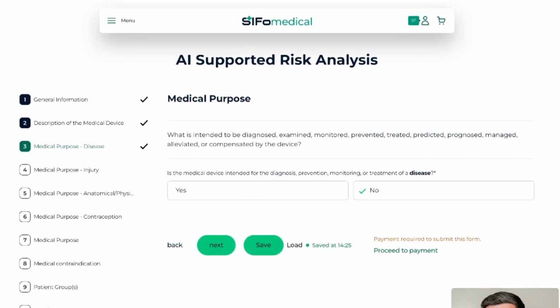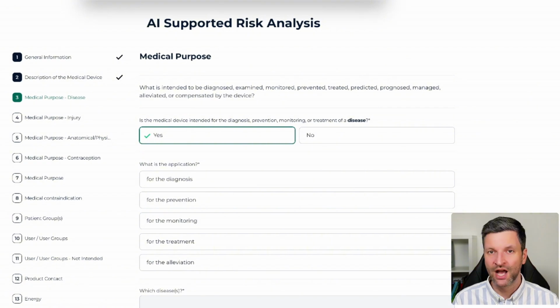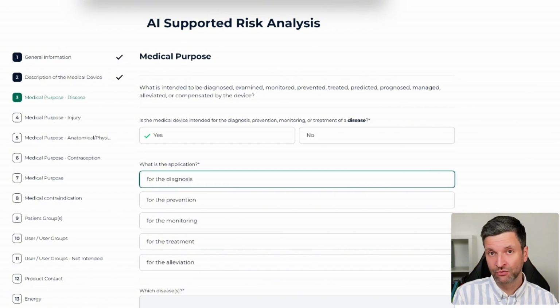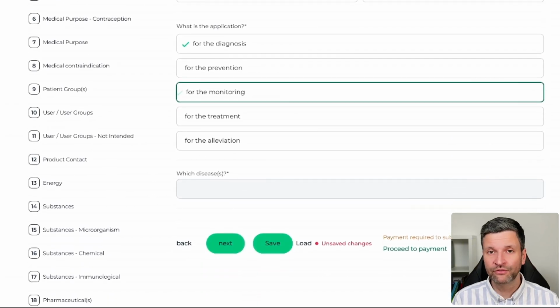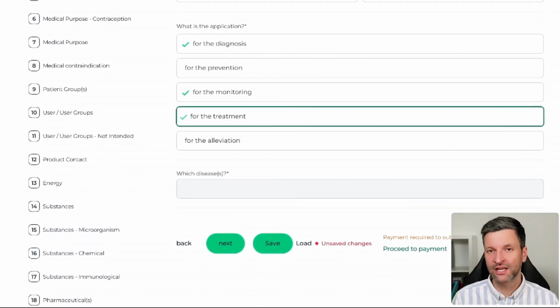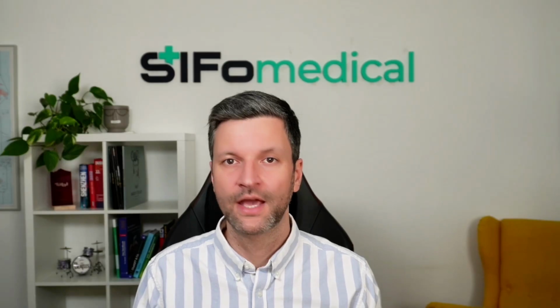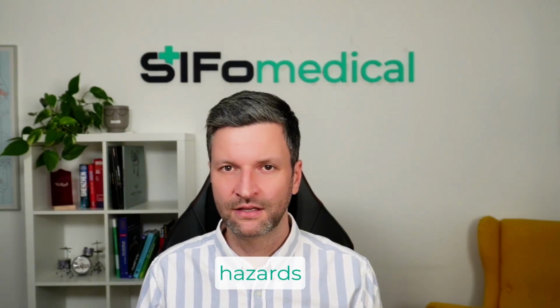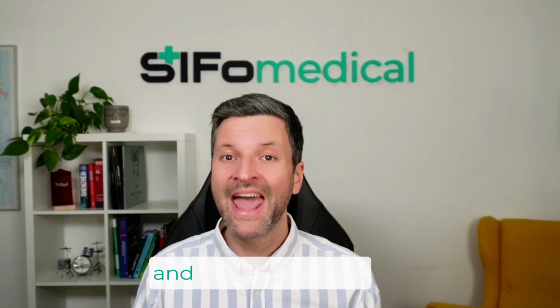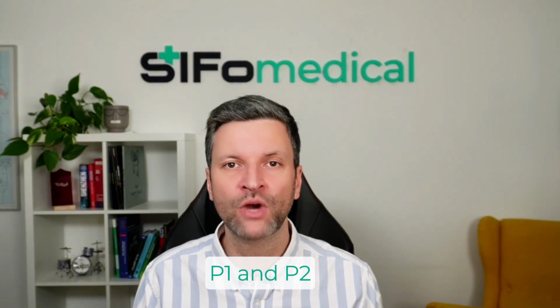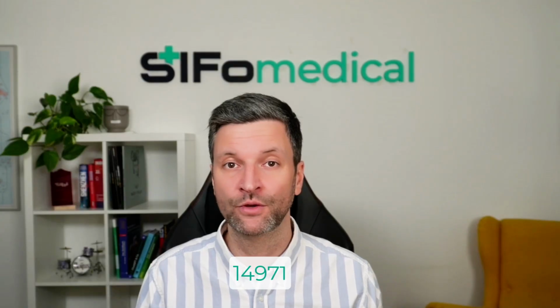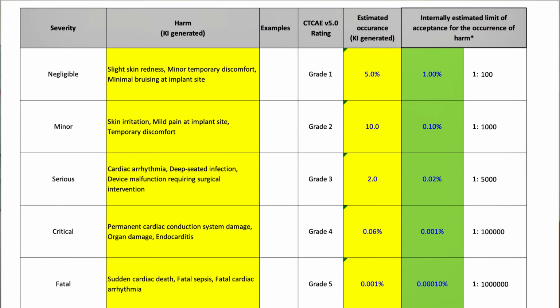Let me show you how this works in practice. You start by answering a structured questionnaire about your device, its intended use, the clinical environment, the user profile. Based on these inputs, the system automatically generates a comprehensive risk analysis. It identifies relevant hazards, defines hazardous situations, assesses potential harms, and calculates initial probability and severity values, P1 and P2, according to ISO 14971.